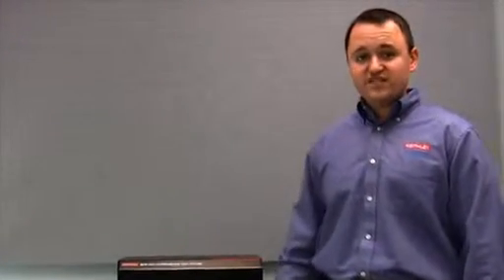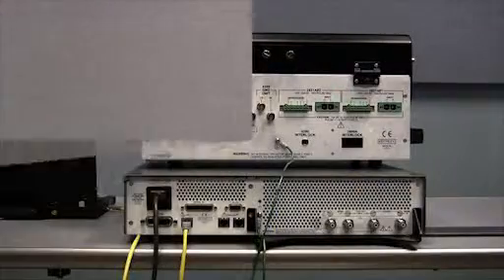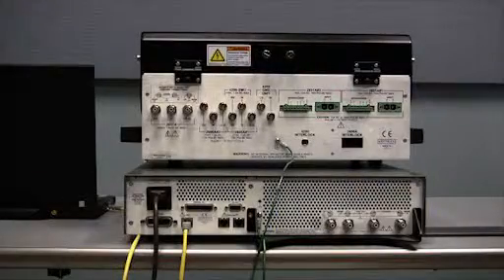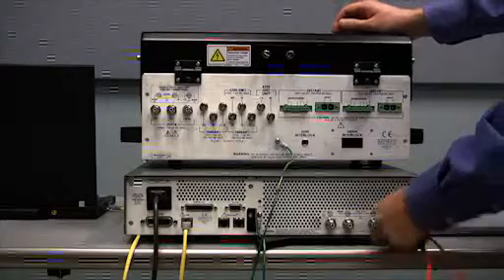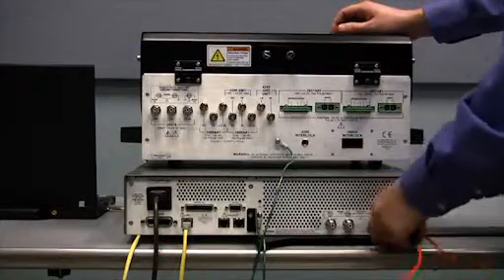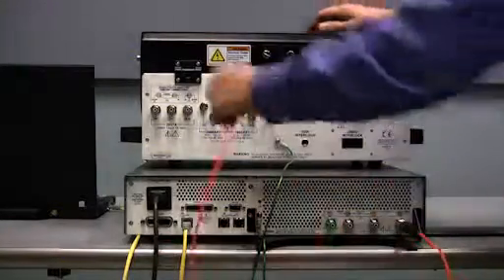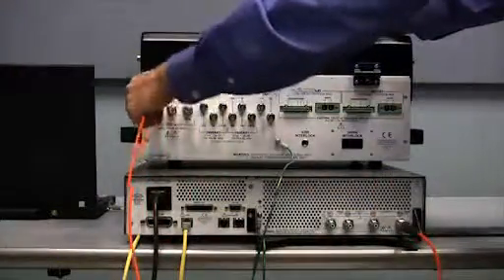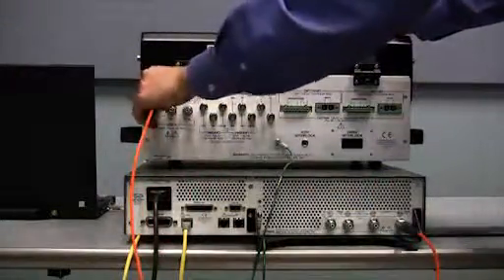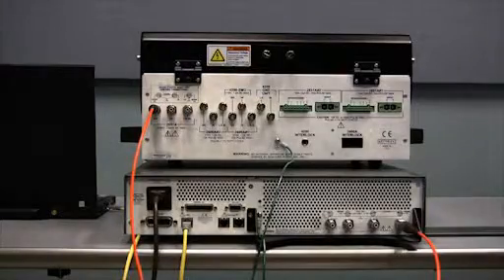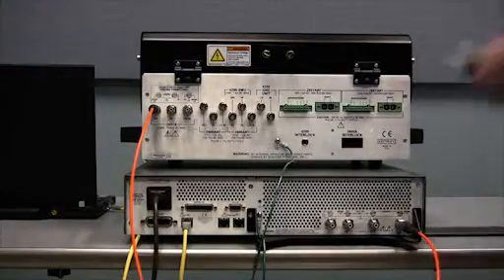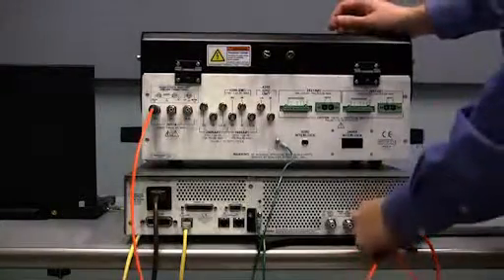Now making connections from the model 2657A to a device is simple using the model 8010 test fixture. First connect the model 2657A to the model 8010 using high voltage triax cables. Three cables provides for four wire remote sensing capability.